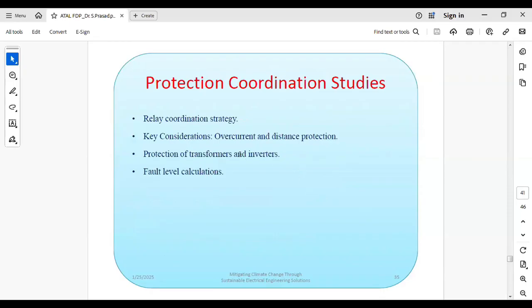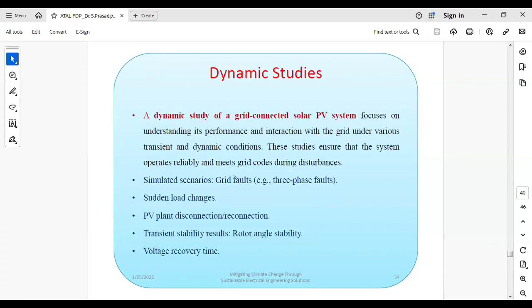Yes, okay. So this is about the transient stability. Just in brief, I'm telling, under dynamic study, LVRT and HVRT tests will come into the picture, and due to shortage of time, I will tell you briefly: low voltage ride through, high voltage ride through. This is the most important task performed whenever you are going for the grid integration, PV plant connection to the grid. Okay, LVRT and HVRT test, low voltage ride through and the high voltage ride through test.